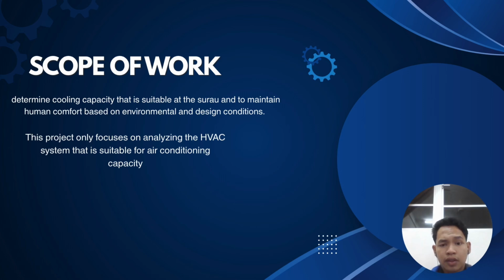The scope of this project is strictly defined to ensure a focused and accurate engineering analysis. We focus specifically on the cooling load demands of Surau Al Hadid based on its unique environmental and architectural parameters. To achieve this, I will gather on-site dimensional data, identifying the construction materials used for the walls, floors, and roof, mapping out the layout design and tracking local weather profiles. The mathematical calculation will be conducted using the CLTD or cooling load temperature difference method, which is preferred by engineers for its reliable approximation of heat transfer through a building envelope.